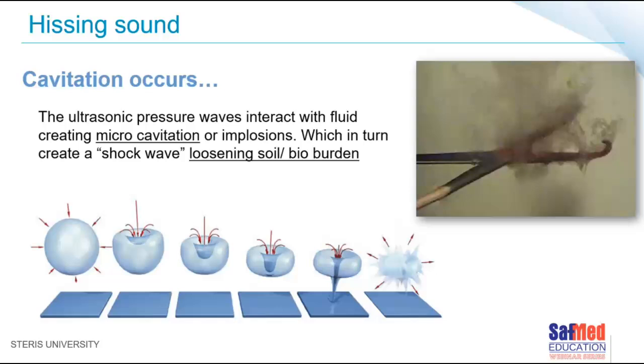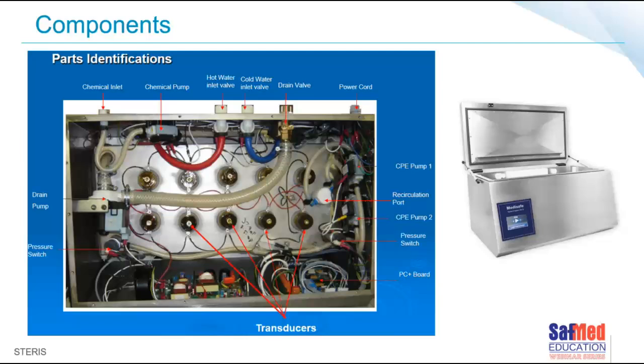Remember all that hissing sound? You can hear it. You can imagine how all these little implosions happen. And that's what loosens all the soil and all the debris in these really complex areas of the devices that we just can't get into. We can't get there with our brush. Looking at the base now, those little round dots that you can see over there, the red arrows are pointing to them, are the transducers. So you can see here we've got 2, 4, 6, 8, 10, 12 transducers sitting at the base of the ultrasonic cleaner. And that's to make sure that we get ultrasonics throughout the bath, that it's not just ultrasonics in one little corner or one part. So very important that we make sure that all of those transducers are actually functioning correctly.